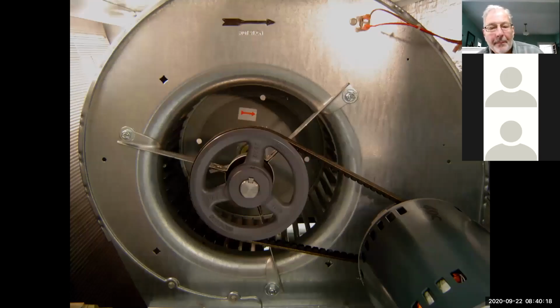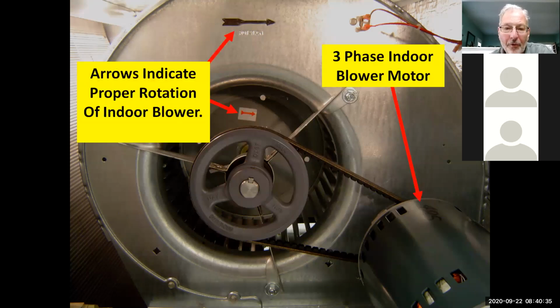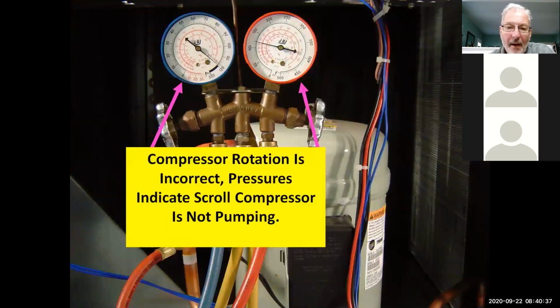On a belt drive model, it's pretty easy. The motor turns with the direction of the vanes on the squirrel cage for checking rotation. Remember I said on the plenum fan models, it's auto-correcting, so don't use the check for proper rotation. And make sure that you check the compressor, okay?